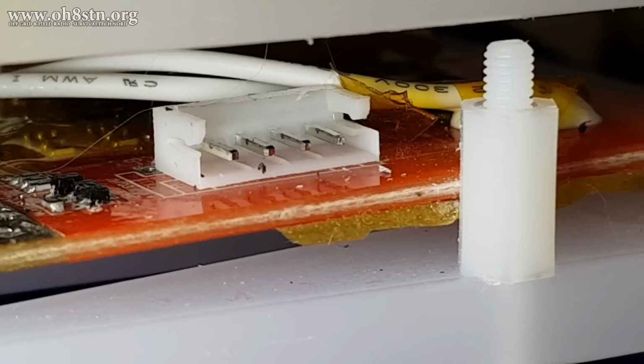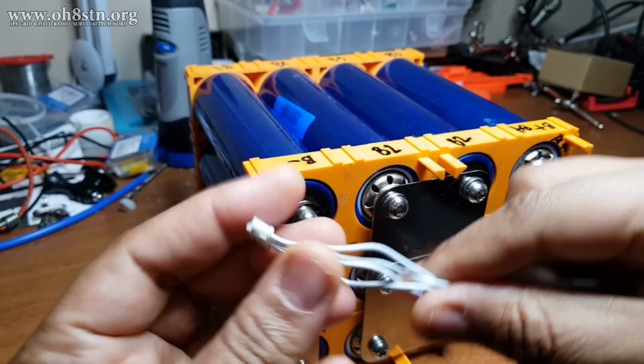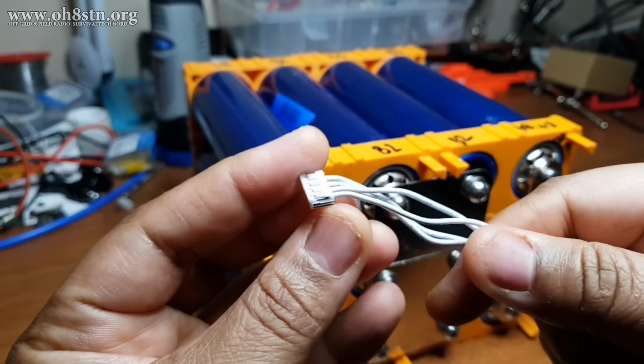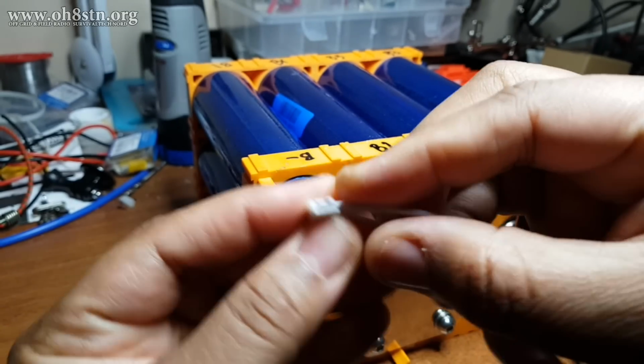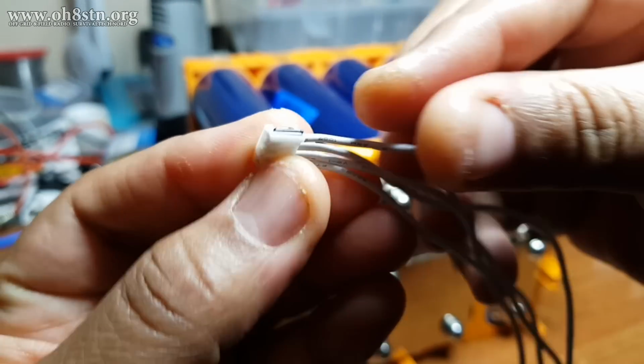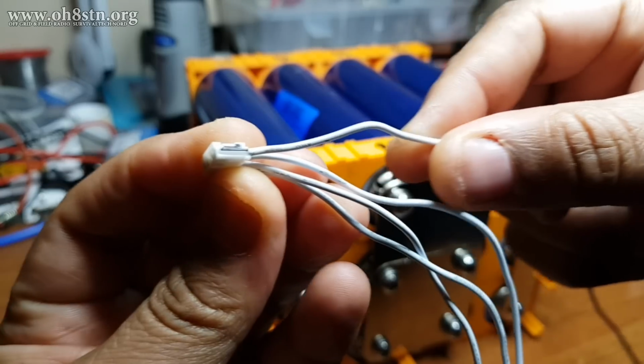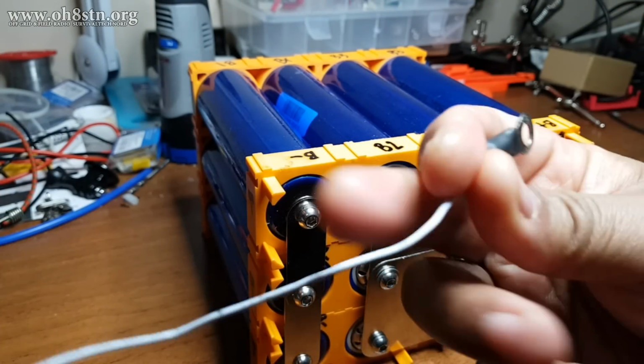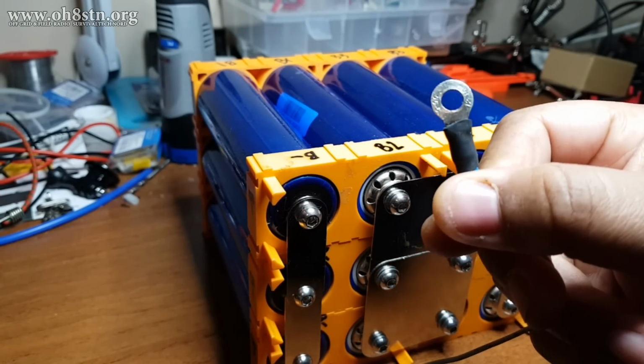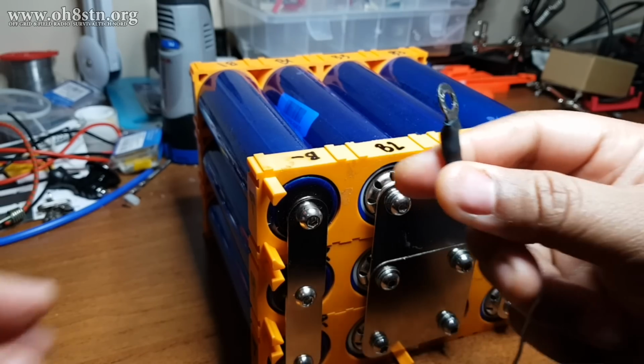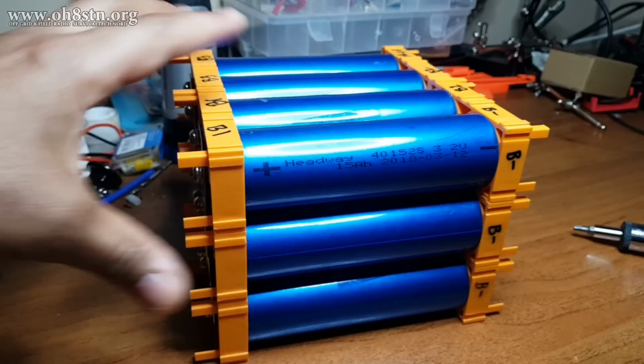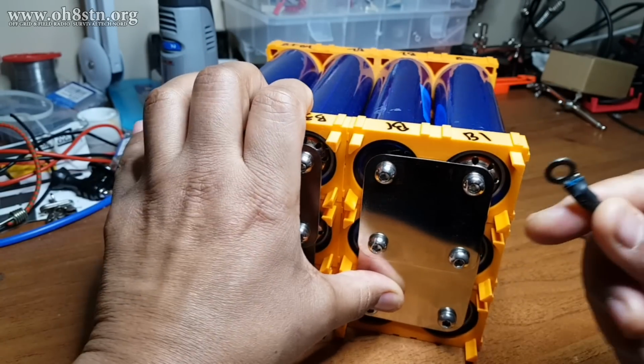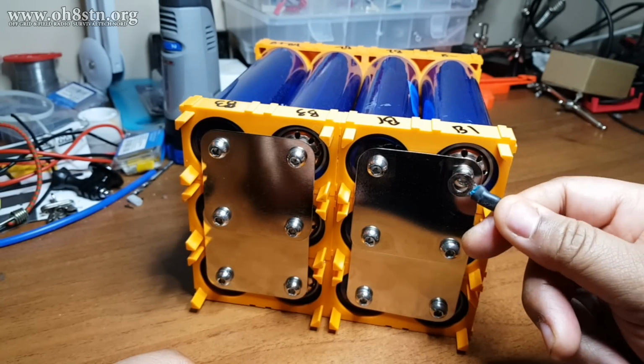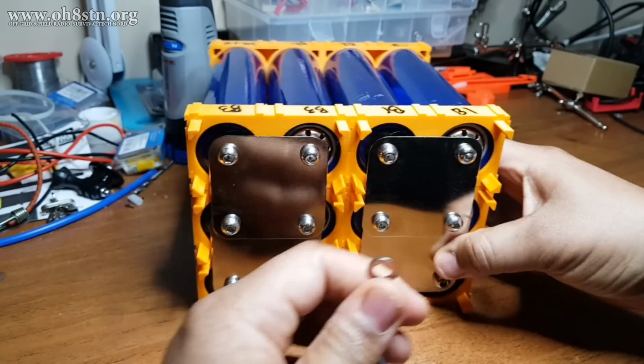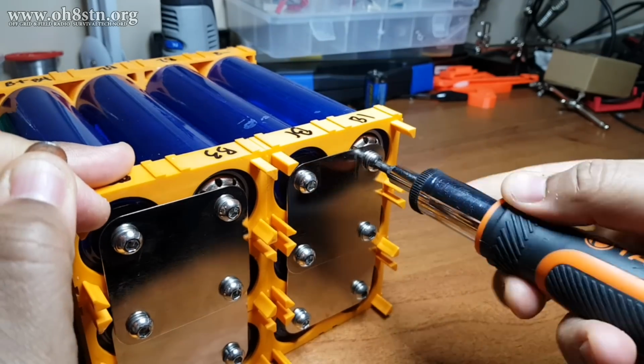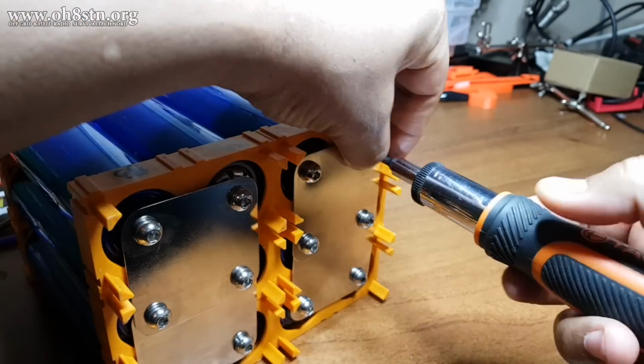So now go ahead and find the mark you placed on the balance lead connector. Remember, we're not going to connect the balance lead to the BMS while we're connecting these leads. Now find that first lead coming off of the mark and connect that to the positive side of your battery minus. That may sound a little confusing, but use the wiring diagram from a couple of minutes ago in the video as a reference.